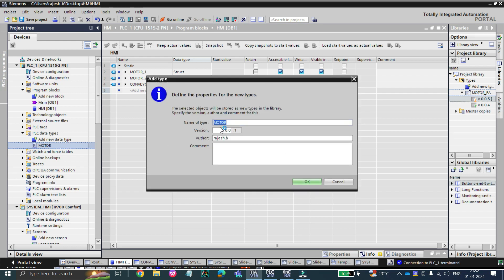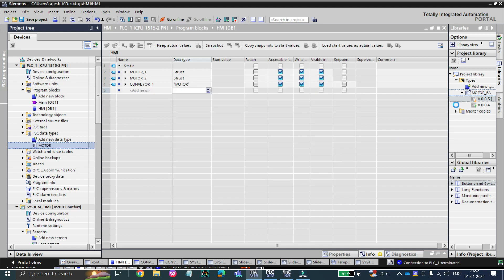Now you can see it will ask what type the motor is — just like we created the faceplate, it will also ask for your UDT. It is asking because this UDT will be used as version 0.0.1, so click OK. If we send any changes to our UDT data type, it will create another version. Now you can see a black mark appearing on your UDT type, and it has also been added to the library.